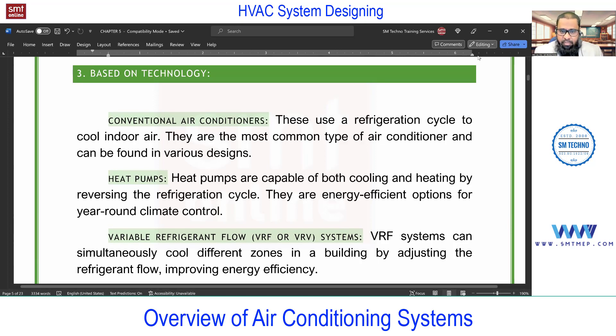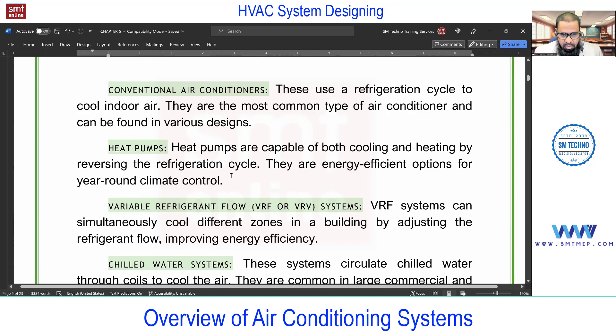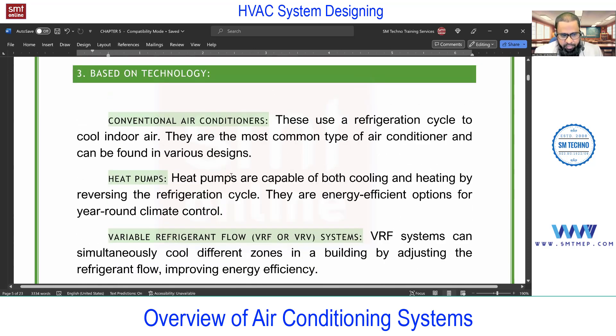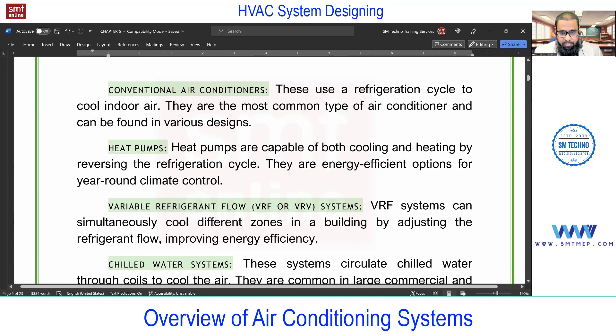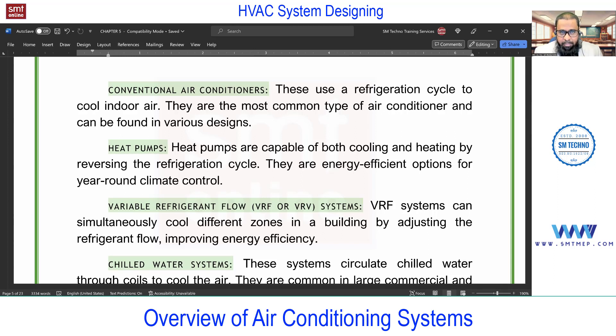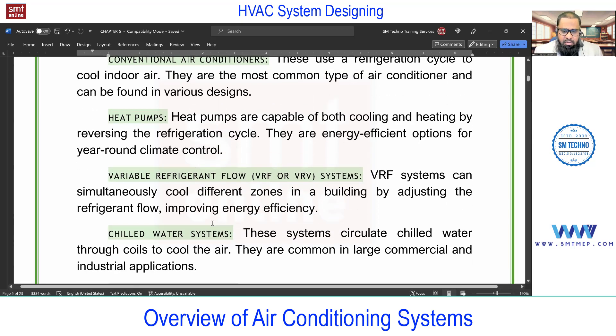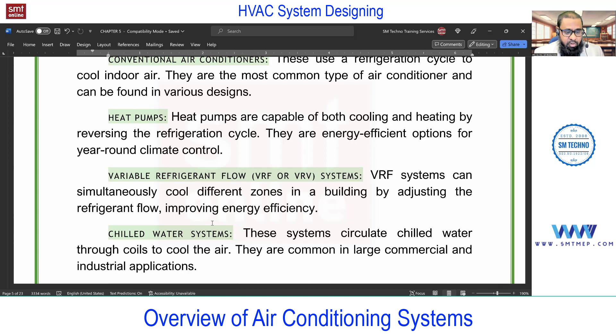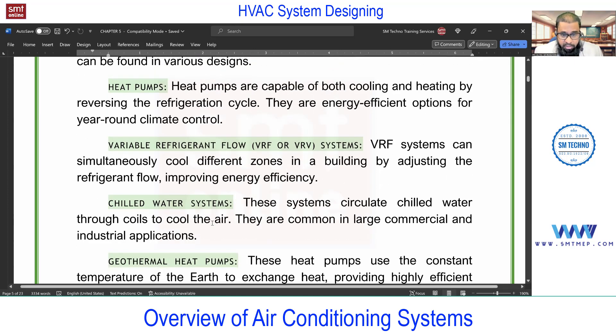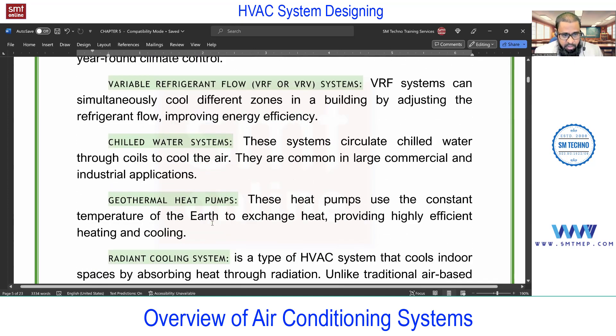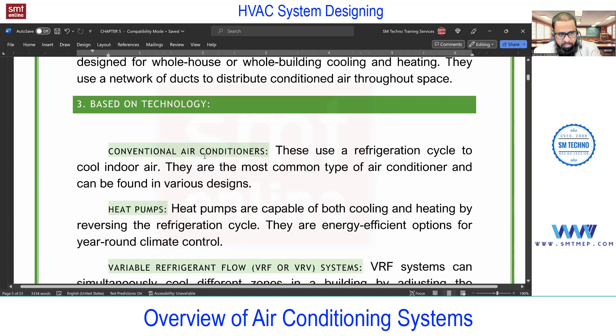Next is the heat pump, which also uses the vapor compression cycle but can work in reverse. Then VRF or VRV — don't get confused, VRF and VRV are the same technology. VRV is a patent by Daikin, so other manufacturers use the term VRF, but from a technology standpoint both are the same. This also uses the refrigerant cycle but in an advanced way, and it is becoming popular in Dubai, India, and many other locations. Next is chilled water — very important — and this time the classification is based on technology, not design.